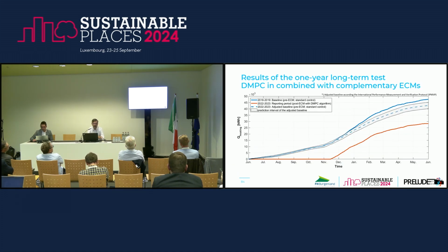The first slide shows you the cumulative energy demand for heating. The continuous blue line is the energy demand for heating of the reference year. The reference year is the year from June 2018 to June 2019. The red continuous line is the energy demand for heating during our long-term test with the DMPC in combination with all other measures which we have taken. And the dashed blue line is the calculated adjusted baseline according to the International Performance Measurement and Verification Protocol. If we compare the calculated adjusted baseline with our measured cumulative energy for heating, we have a reduction of 34%, more or less 14,000 kilowatt hours of energy demand.